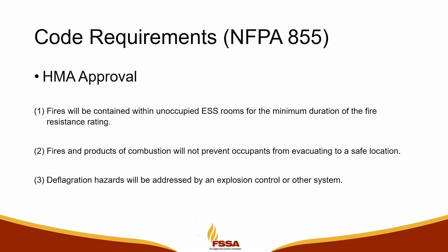The code does a really good job talking about hazard mitigation approval — there are different ways we can approve these HMAs. One key requirement: deflagration hazards must be addressed by an explosion control system or equivalent. That's huge for us, because we know these batteries create enough flammable gases to create an explosive atmosphere, so we want to make sure deflagration hazards are addressed in the HMA before I can approve it.